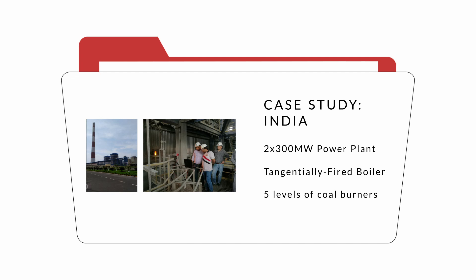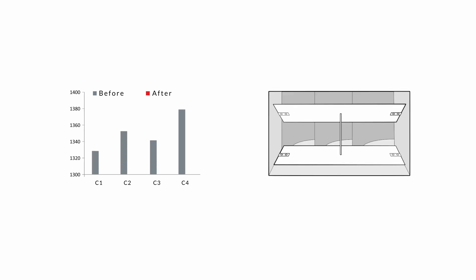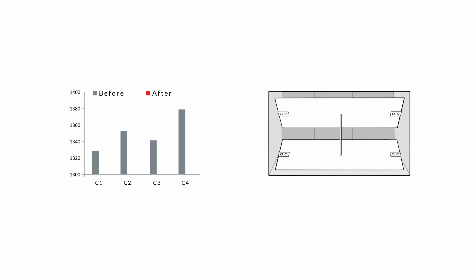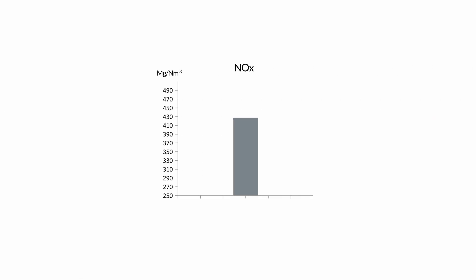Temperature profiles were collected from 12 viewing ports. Based on the temperature data analyzed by TempVision 1000 software, two of the secondary air dampers were adjusted to balance the temperature distribution. As a result, the NOx reading reduced from 422 to 345 parts per million, an 18% improvement.